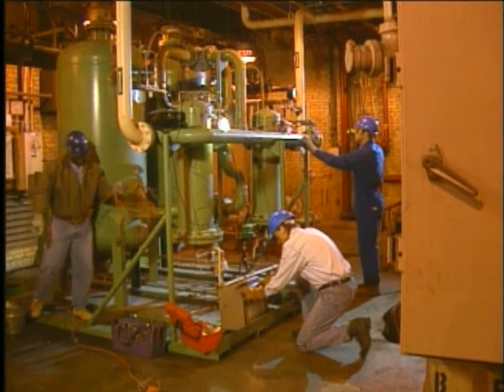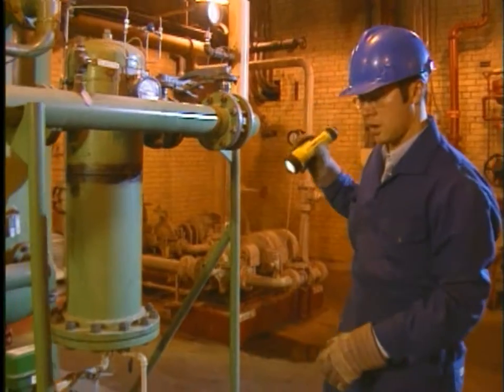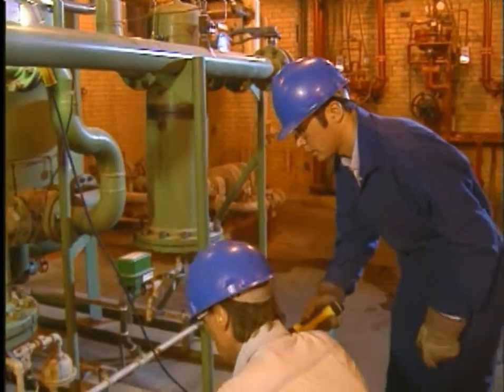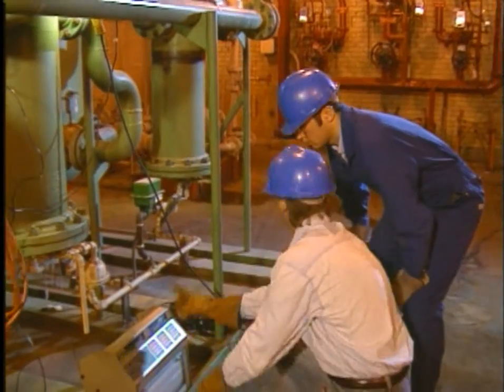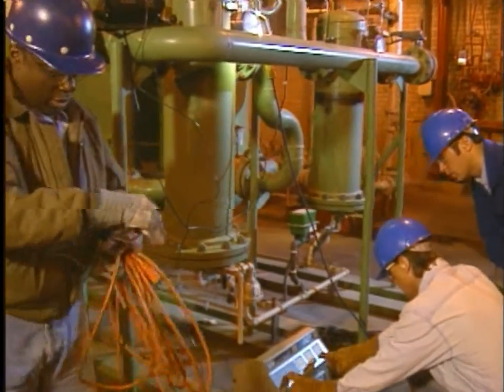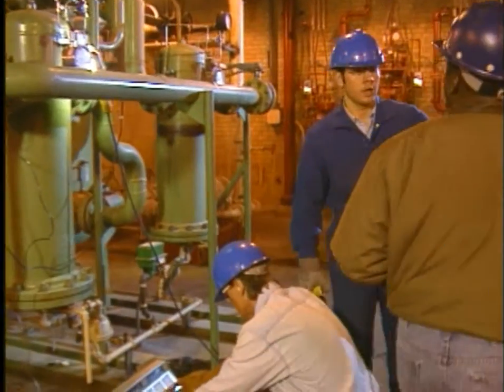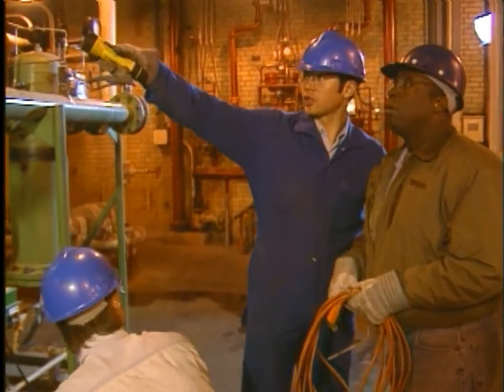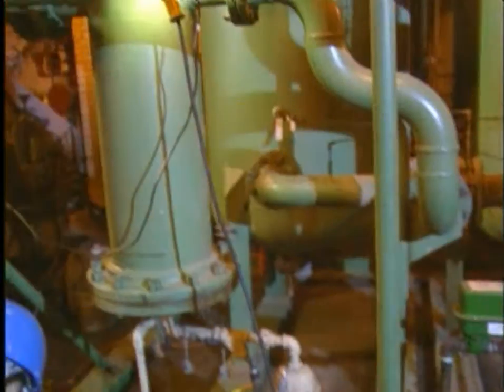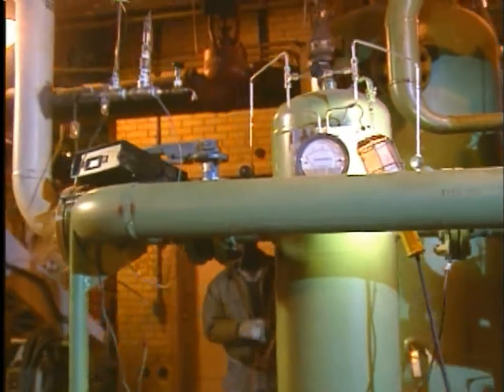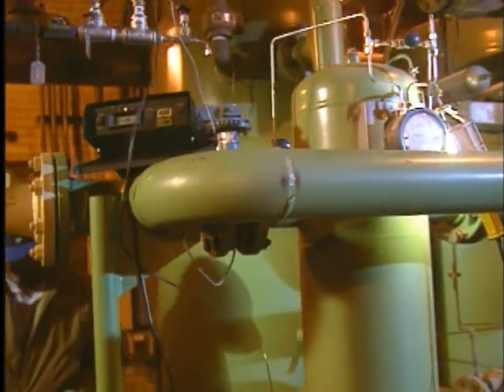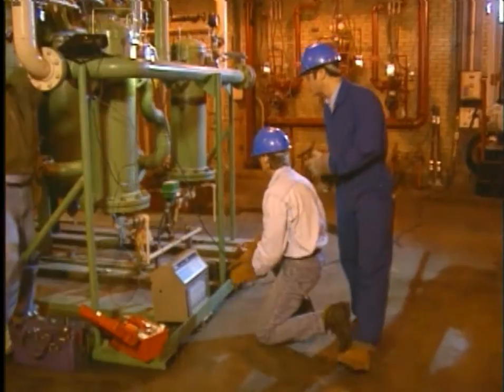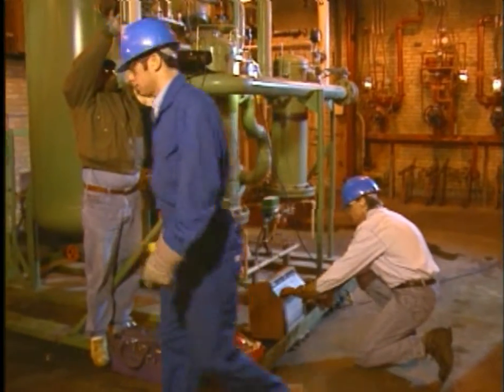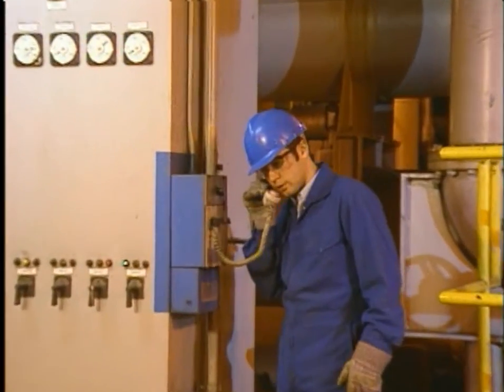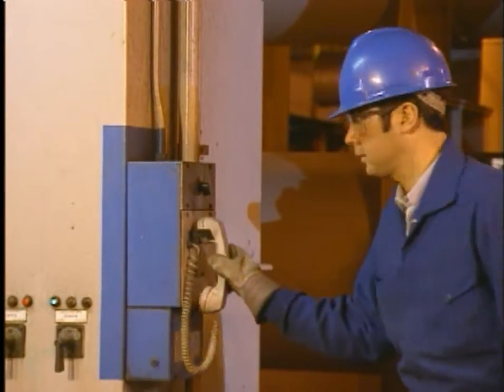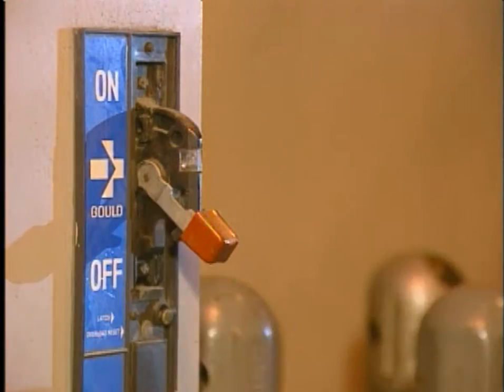When work is complete, first inspect the entire work area to be sure all tools, jumpers, grounds, and other devices are removed. Then, warn co-workers to stay clear of the equipment being returned to service. Remove locks and tags from energy isolating devices to restore energy. Ensure equipment is safe to operate with all guards installed and blocks, braces, and grounds removed. Count workers to be sure everyone is clear of equipment. Notify everyone affected that the system is being returned to normal operation. Remove locks and re-energize.